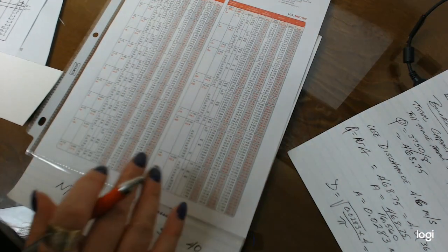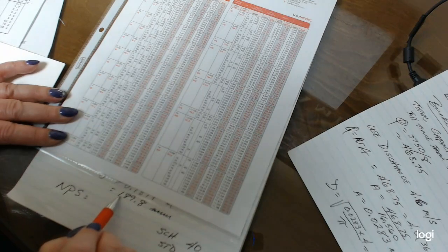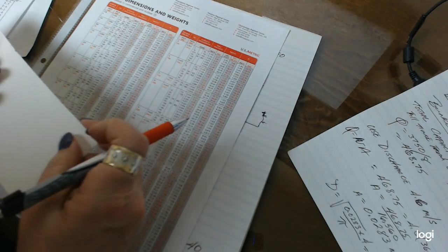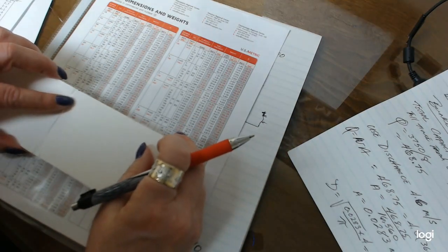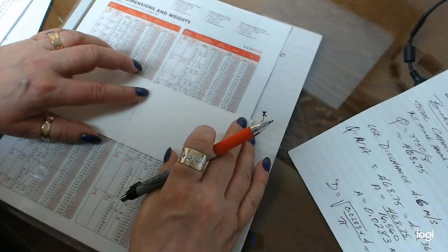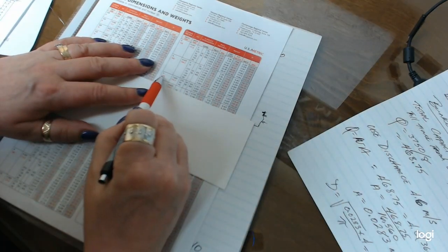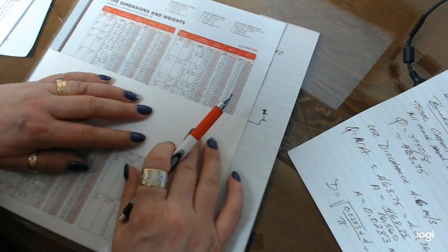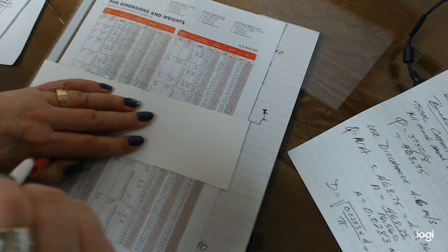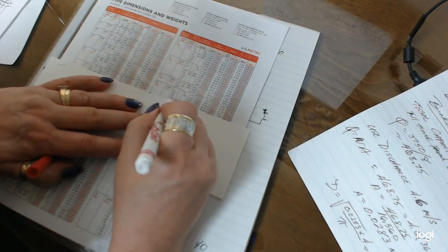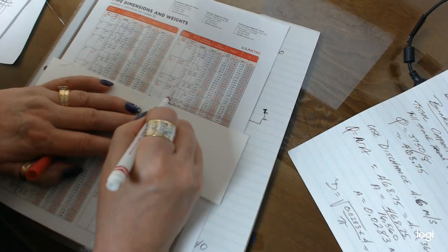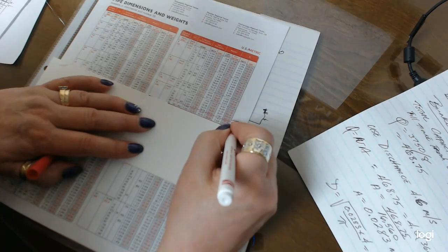So I'm going to look for something that's in the vicinity of 189 millimeters. I'm just looking at the time here. And when I look at this, I can see that 175 or 7-inch pipe is in the vicinity, but I'm looking closer at 8-inch pipe. I go down to my standard and I see here that right across here I have a pipe size that I can use.